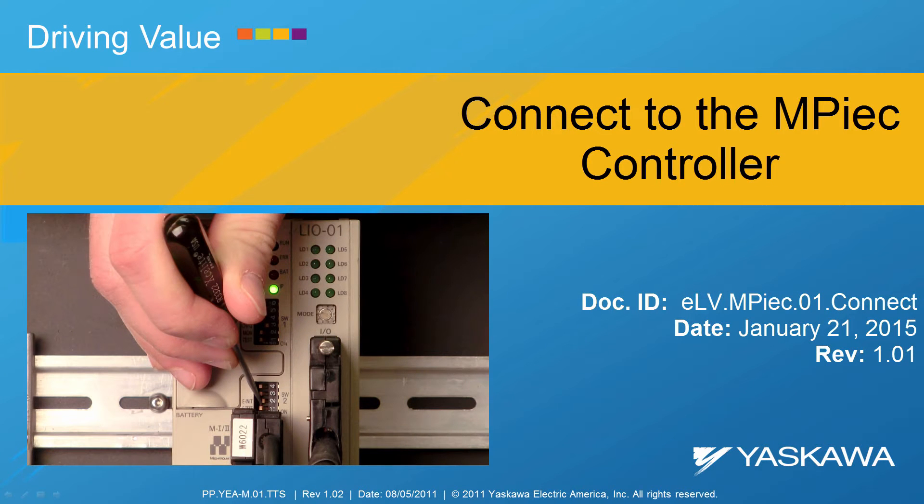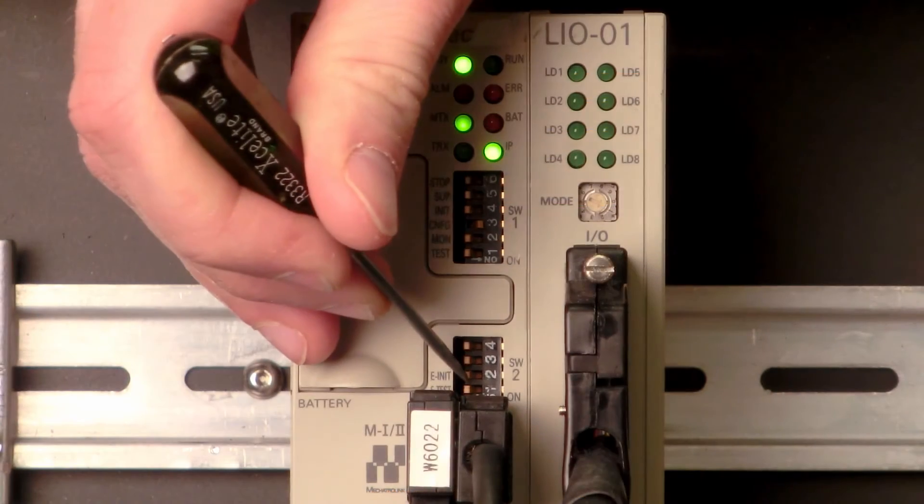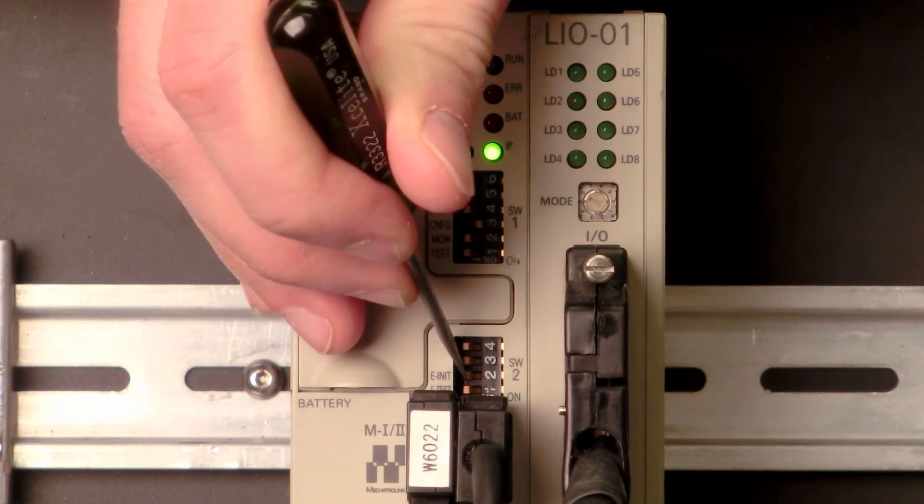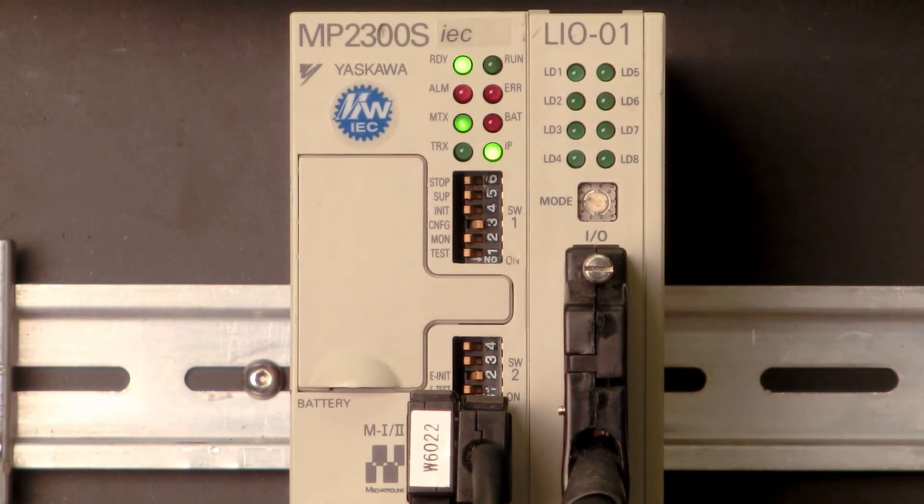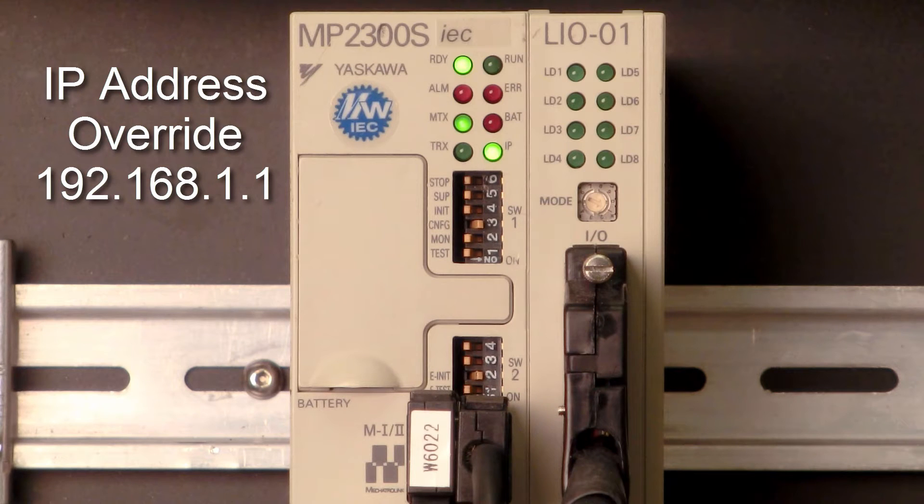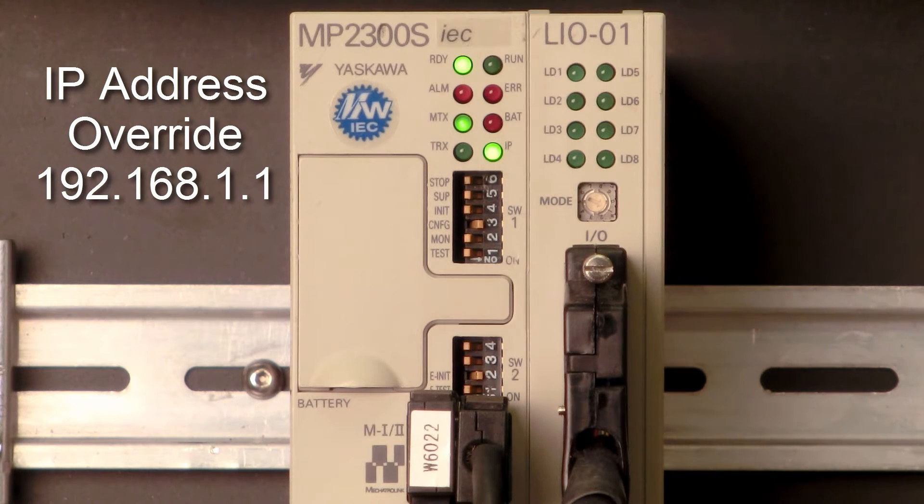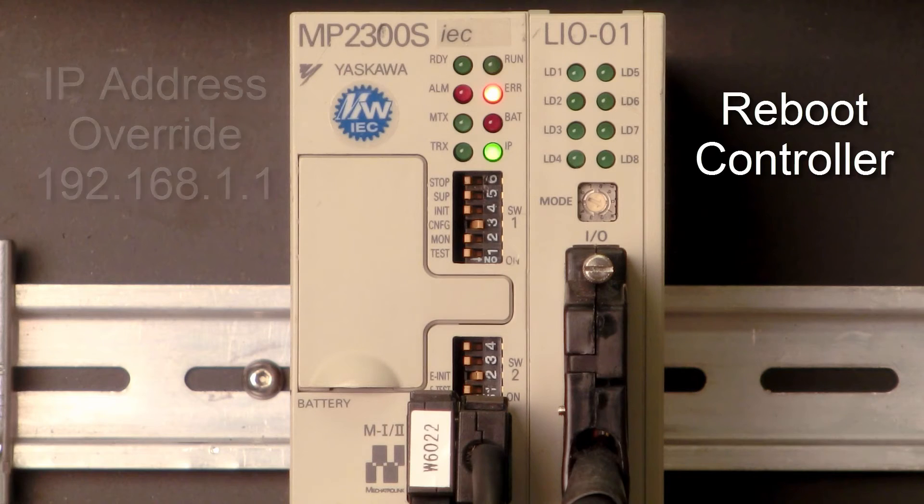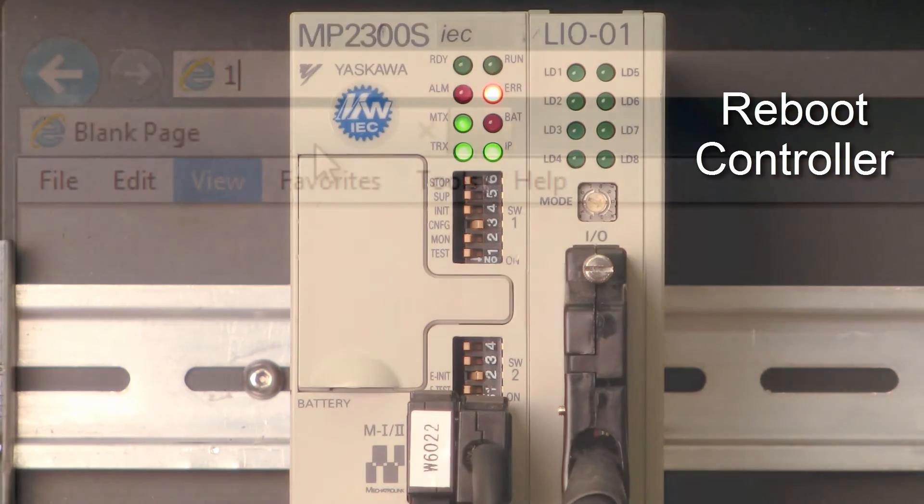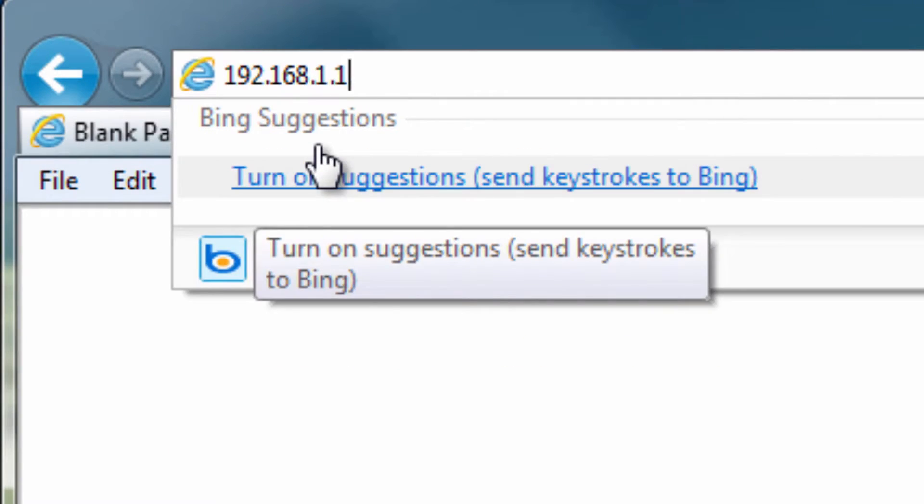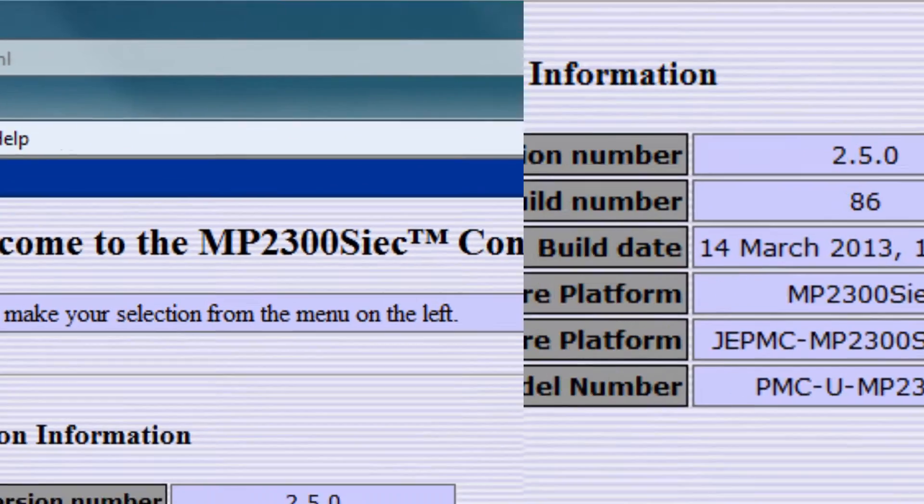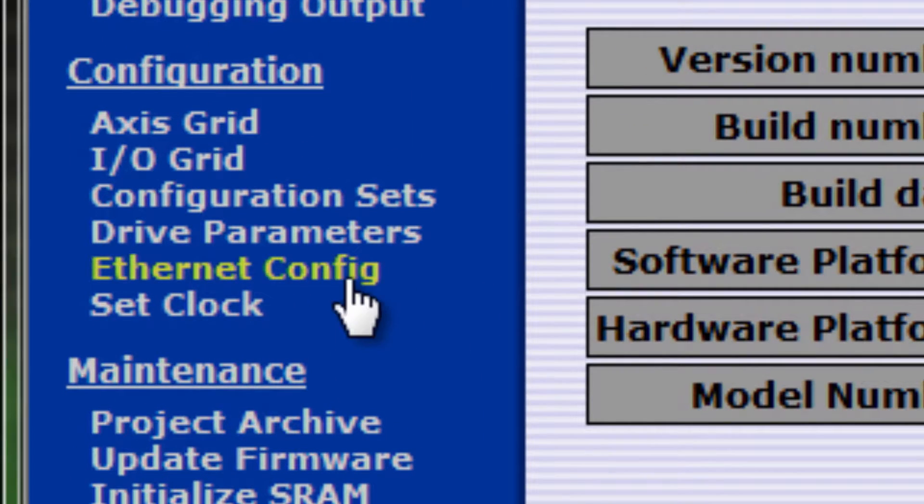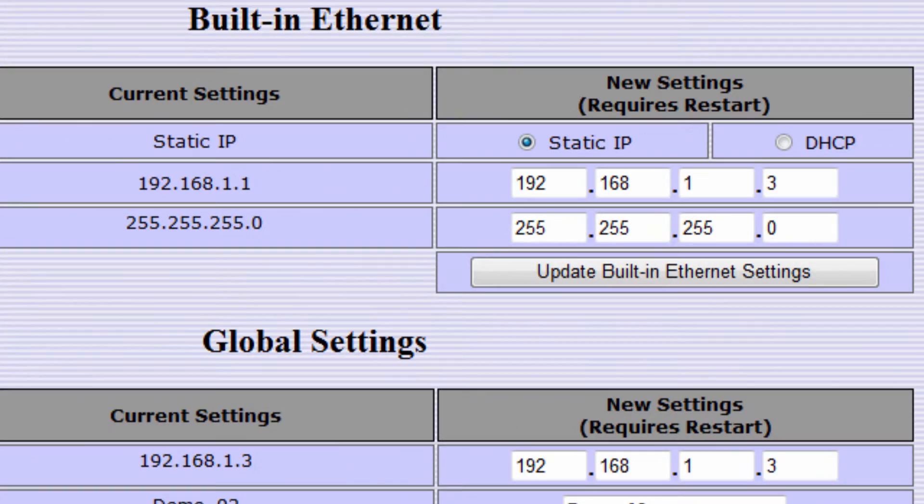This video shows how to connect a PC to an MPIEC controller even if you don't know the IP address. Here's a quick preview. The controller IP address can be temporarily overridden to 192.168.1.1 at any time by rebooting with the EINIT switch on. Test the connection with Internet Explorer by entering this address. Then use the controller's built-in web page to configure the IP address that will be used when EINIT is off.